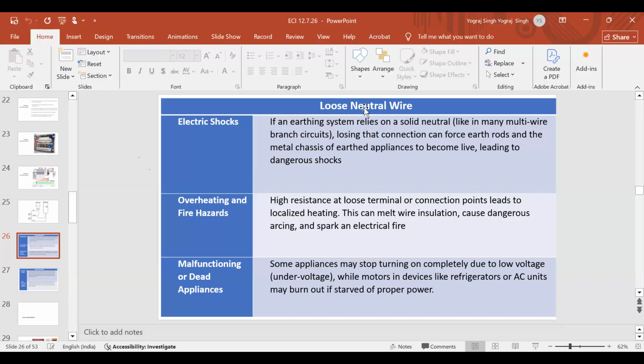Then, when the neutral connection breaks, power finds alternate return path through other connected load. As I had shown, suppose neutral is not properly connected from table lamp side, so still it will get return path through refrigerator. So when this happens, there will be problem. Voltage imbalance will be there. This causes some severe voltage imbalances, and some outlets may only provide 70 volt, whereas others will spike to 200 volt. So this is a US system where supply system is 110 volt. So 200 volt is dangerous over there. In our case, 200 volt is good enough.